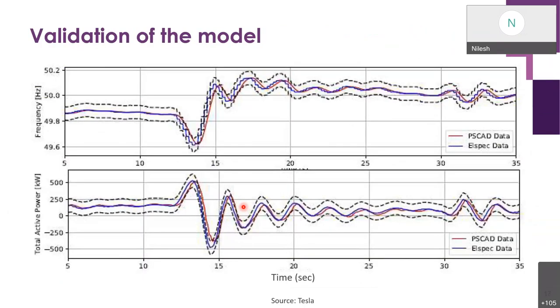And this is the last slide, validation of the model. So this is the validation of a grid forming model against the real time event. You can see, sorry about the quality of this graph, the real time response measured by the meter is in blue, and the reddish line is the response from the model. And they're largely aligning, and the two dotted lines are a 10% deviation from the response.